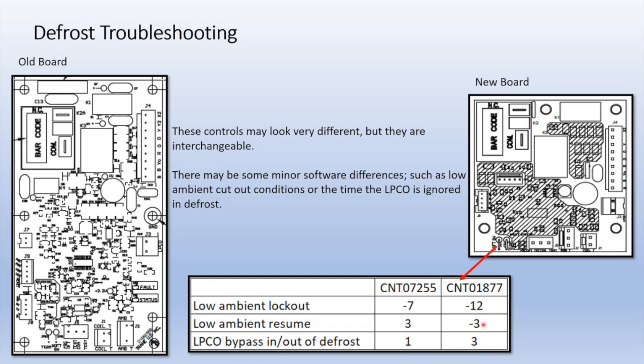So if you do have a system where you have random LPCO lockouts on a heat pump, and you've checked that your charge is correct and everything else is running properly, you may want to just put a new board on it. But don't go to the new board right away. Verify everything else is working properly first.